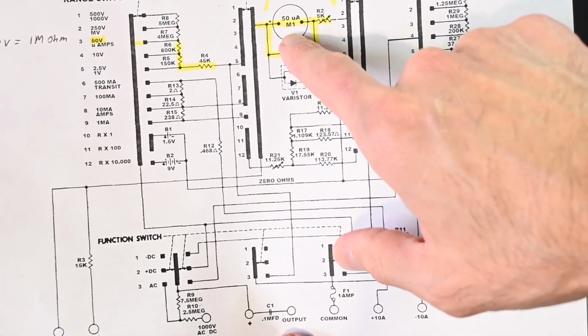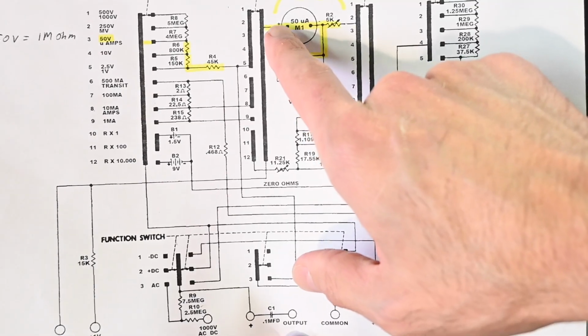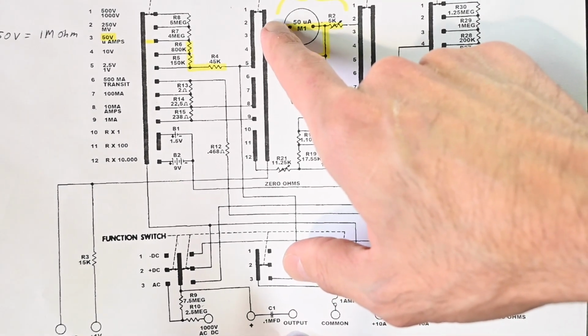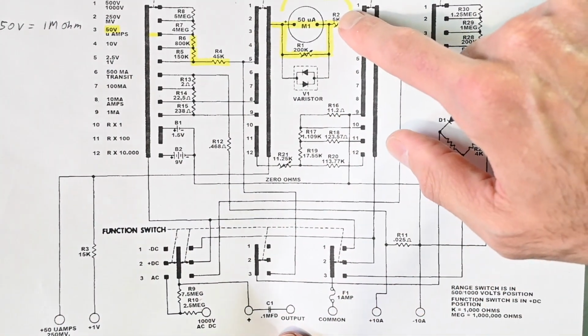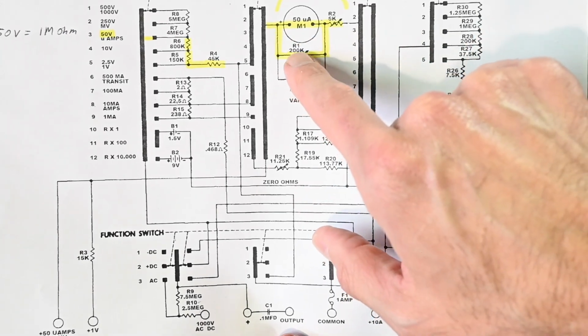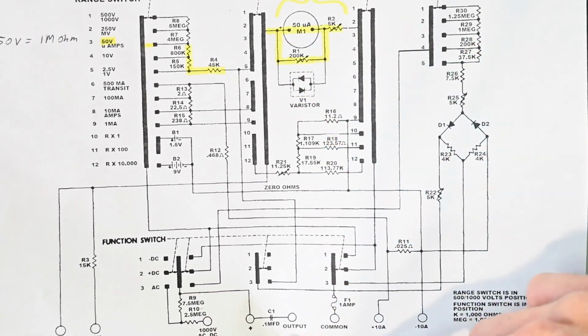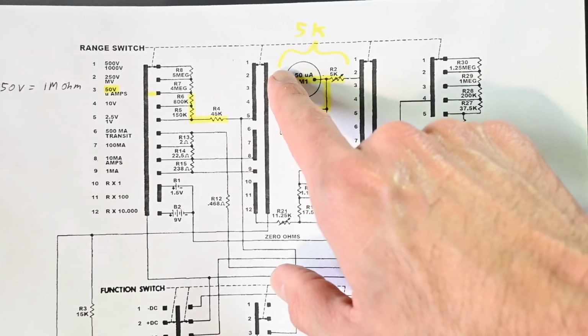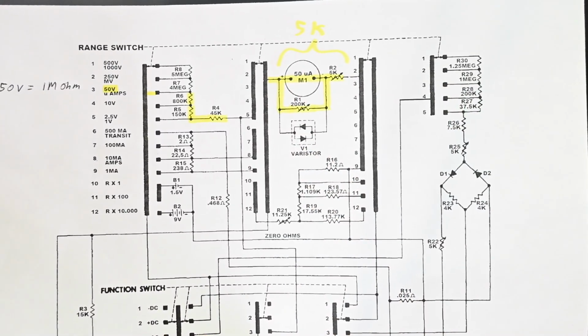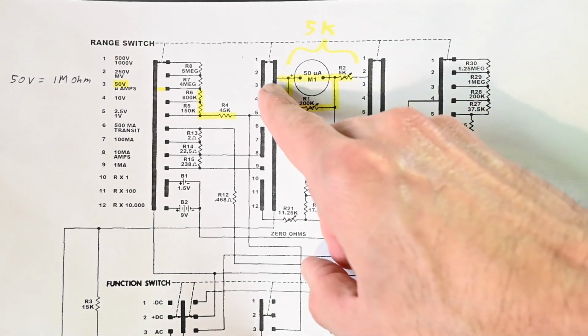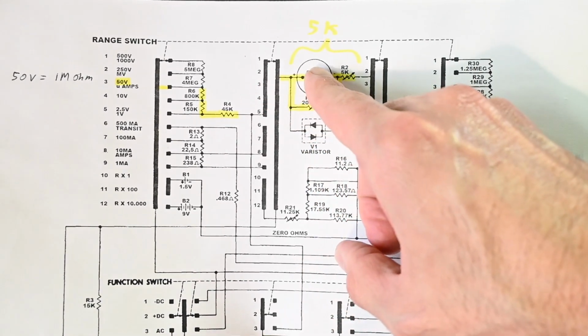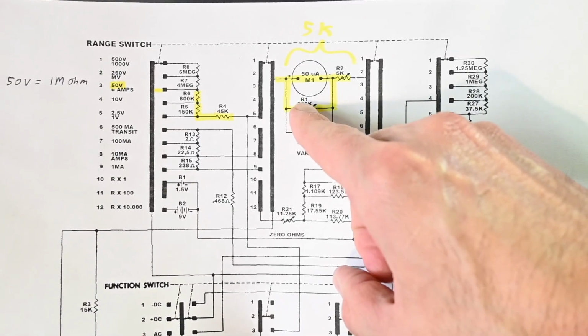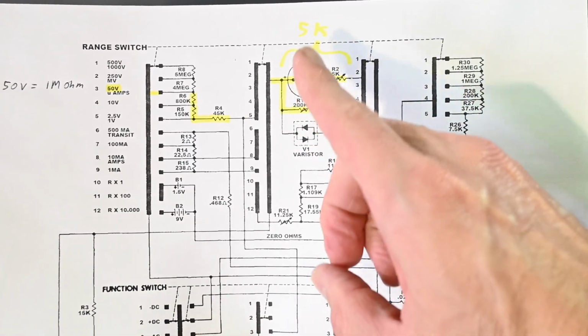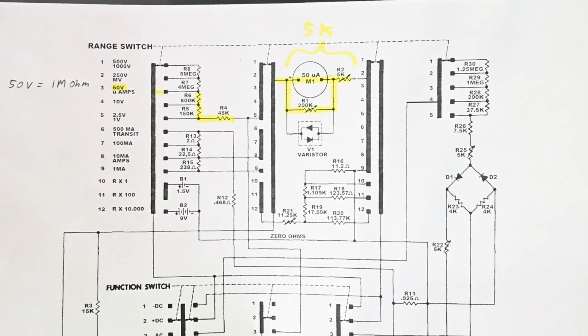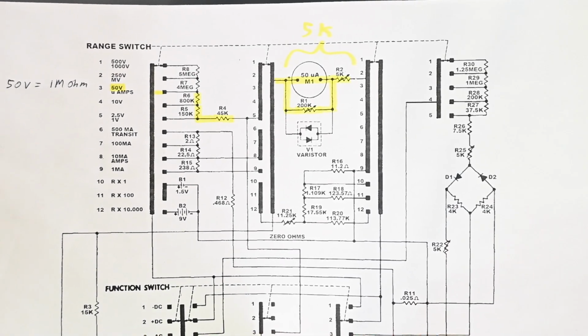So what we want to do is connect the Keithley 236 from this point to this point. So we're not concerned with anything else on the schematic, not even this resistor right here, only the meter and this 200K potentiometer that's in parallel with the meter. And what we're going to do is have 50 microamps, so the Keithley 236 is going to be in the constant current mode, and we're going to have 50 microamps flowing through the meter and this potentiometer, and adjust this potentiometer so that the meter indicates full scale right on the last tick mark on the meter, or on the right hand side, could say at the first tick mark on the right hand side.